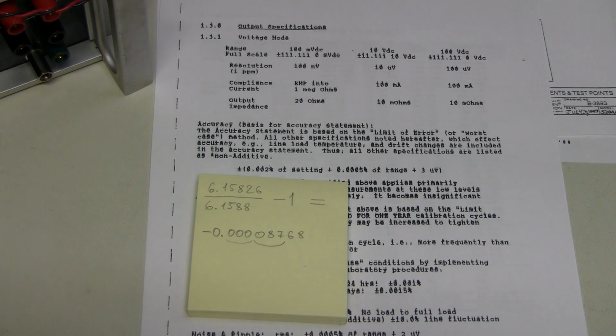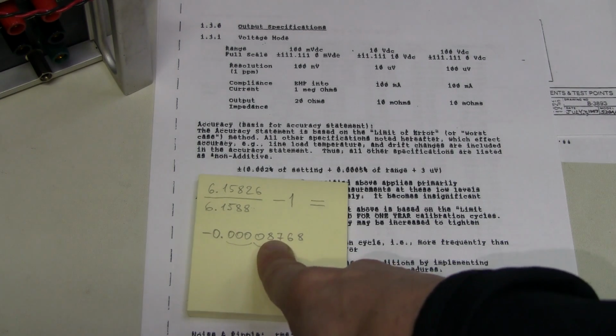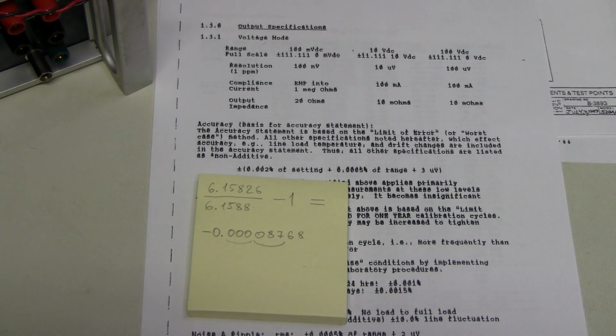So we have about 40 ppm roughly of uncertainty about the meter, and about 20 ppm of uncertainty about the calibrator. And you see, the meter is not really appropriate for this job, because it is less accurate than the unit we are trying to test. But that's the best thing I can do at the moment. So we have a total of about 60 ppm of uncertainty, and we are more than that out. I'm not quite happy about this, but it's not too bad considering that the unit was manufactured in mid-80s, and I have no idea about history of calibration and adjustments and stuff like that.